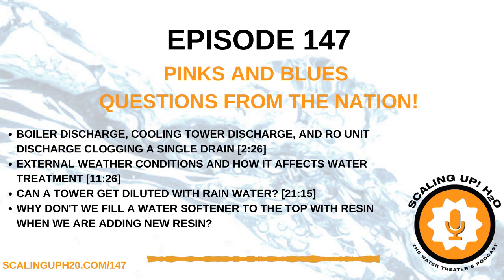I read somewhere that you should backwash your water softener every week, even if the sodium is not exhausted, to prevent channeling from forming. Now, I've also heard from one of my mentors that this should be every 2 weeks. Here's what I learned from that. When you have different water treaters out there, you are never short for different opinions. So I have always sized my water softeners to regenerate about every week, and I always use a twin system on a boiler. So what is a twin system? So this is where we have one resin tank that is online and the other tank is on standby waiting for that first tank to start the regeneration process.